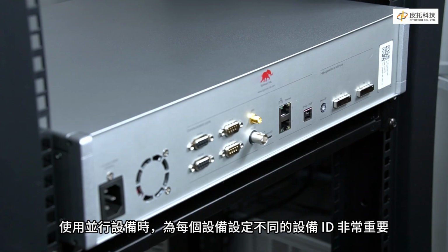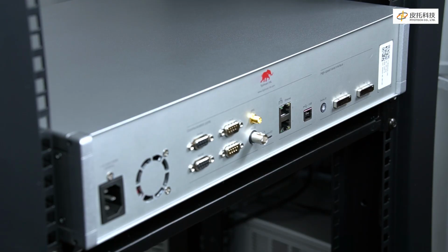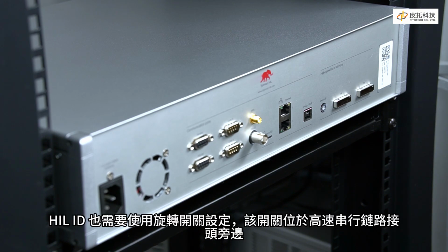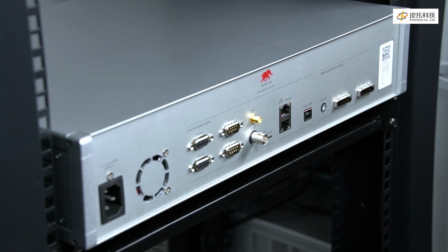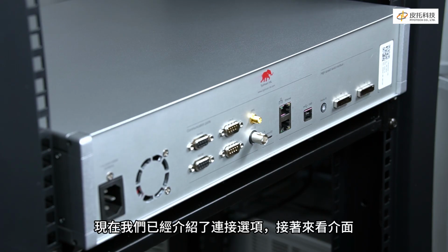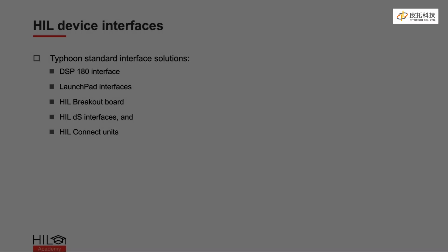That communication is enabled via a high-speed PCIe 5 GHz serial link. It is important that you set the device ID to be different for each device when using parallel devices. The HIL ID should be set with a rotary switch, which can be found next to the high-speed serial link connectors. Now that we've covered the connectivity options, let's look into the interfaces.